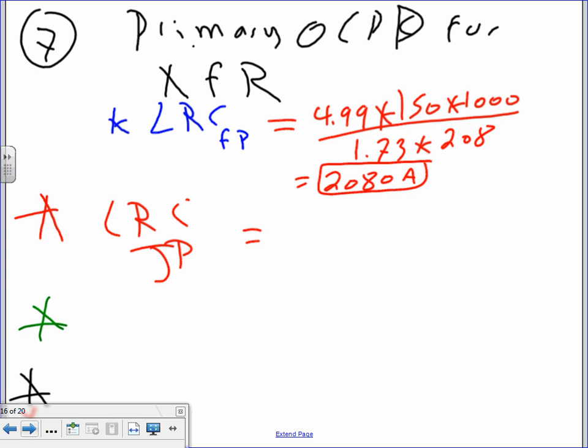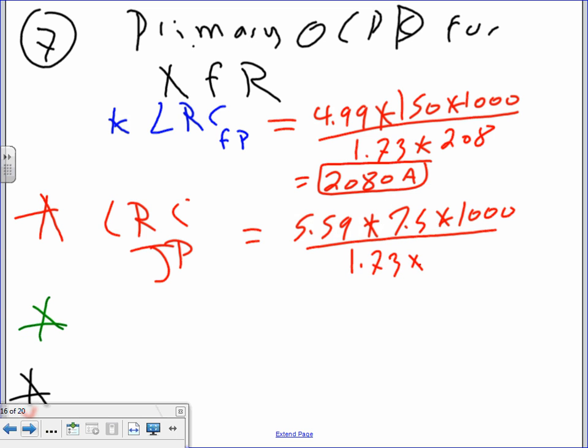You go to the jockey pump, apply the same thing for the jockey pump. It's 5.59 from the table that gives you the lock rotor current, times 7.5 times 1,000. Divide everything by 1.73 times 208 voltage system, and that will get me a 117 amp.